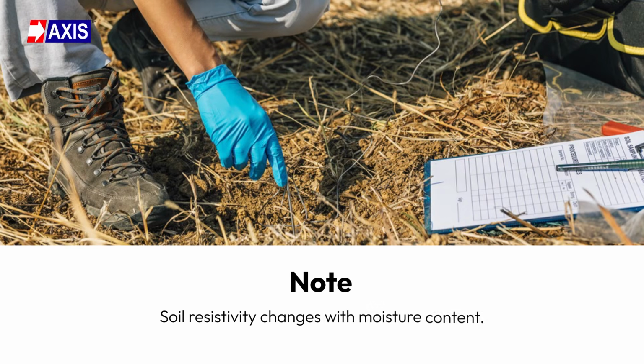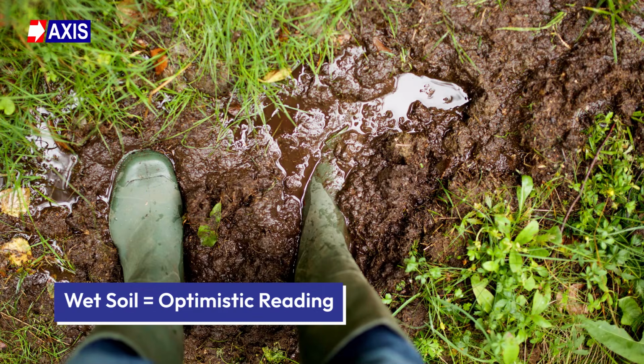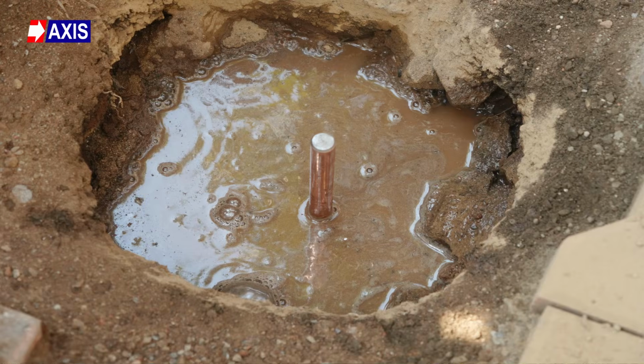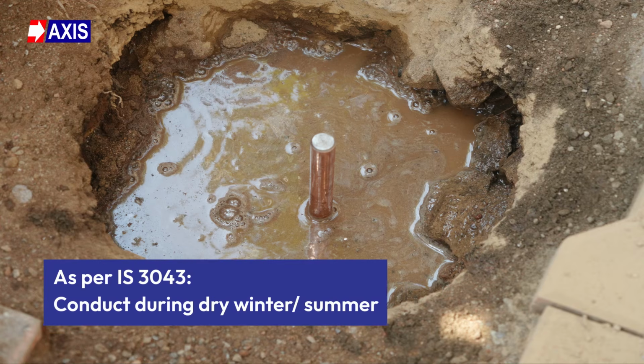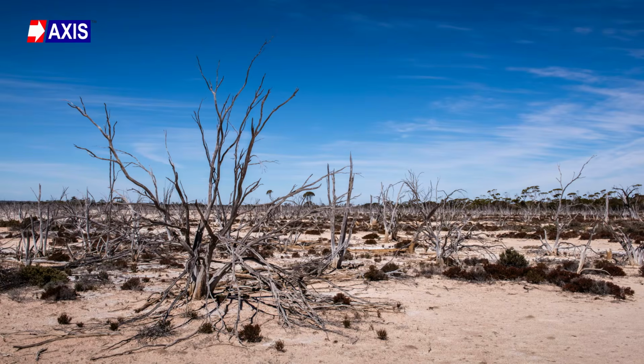Note: soil resistivity changes with moisture content. A wet soil gives you an optimistic reading. To get conservative results, the kind that lead to a reliable earthing design, IS 3043 recommends conducting this test during the dry winter or dry summer season.